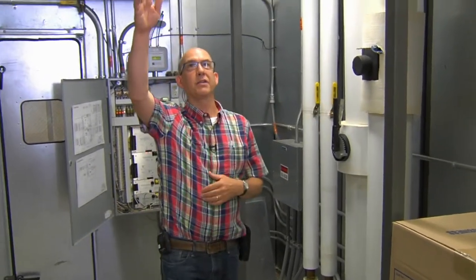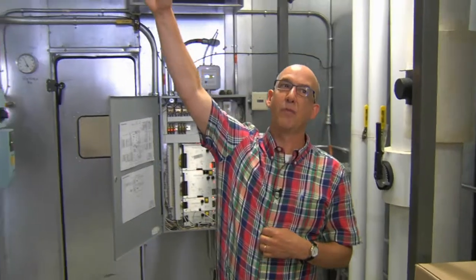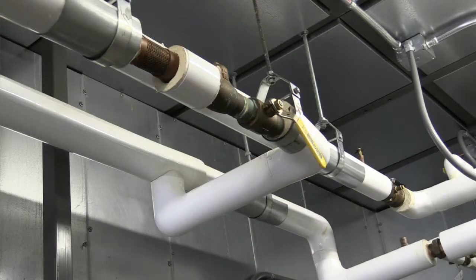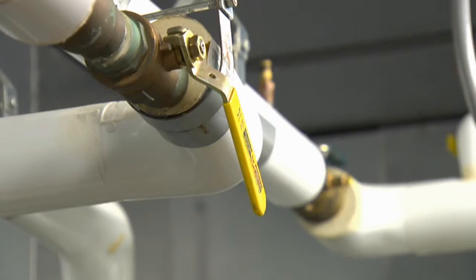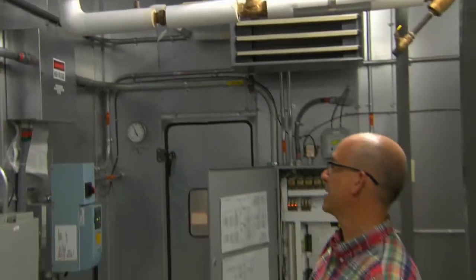Right above me here is a pump with an isolation valve that we can see has been partially closed. And when we find valves that are partially closed like this, that usually indicates there may be a balancing issue and someone's trying to reduce flow on the pump. The pump is further back. That puts a restriction in the line. That's not the best way to solve a problem. That might be a short-term fix.